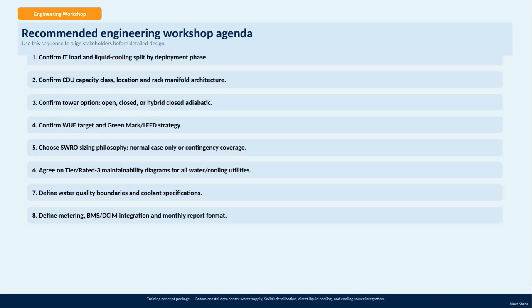This slide outlines a recommended agenda for our upcoming engineering workshop, which is critical for aligning all stakeholders before we move into detailed design. The focus will be on the Batam Coastal Data Center project and covers key elements such as a water supply, seawater reverse osmosis desalination system, direct liquid cooling, and the integration of cooling towers. The next steps are clearly defined to ensure we cover all essential technical decisions. First, we need to confirm the IT load and how the liquid cooling will be split across each deployment phase, which is fundamental for capacity planning.